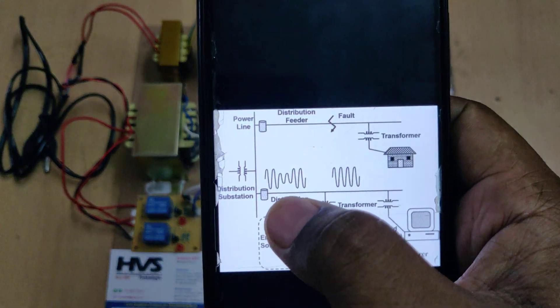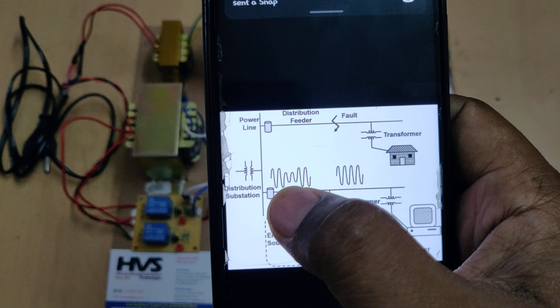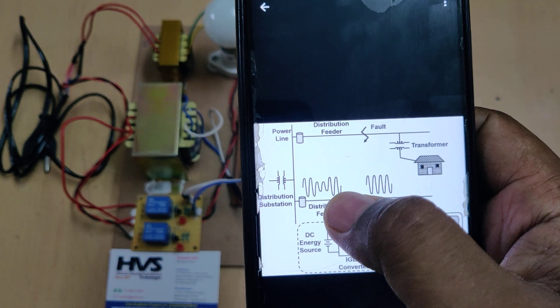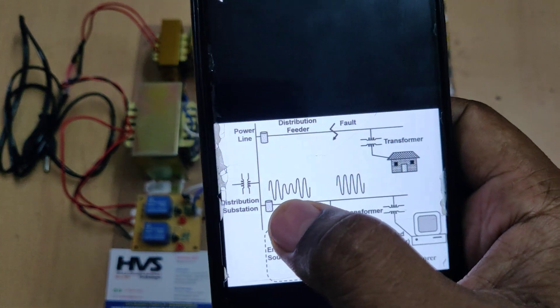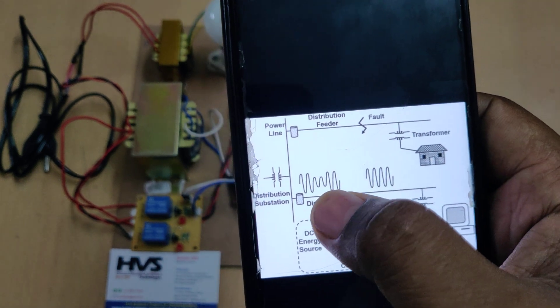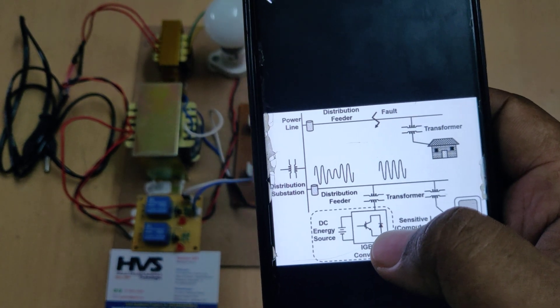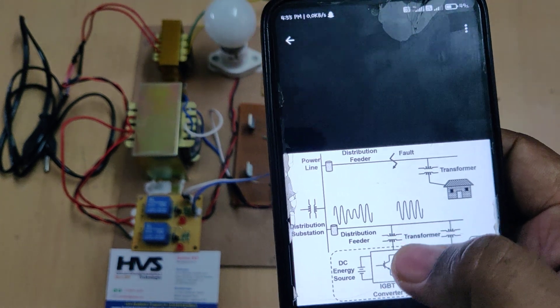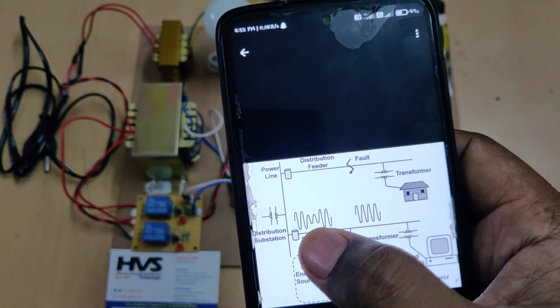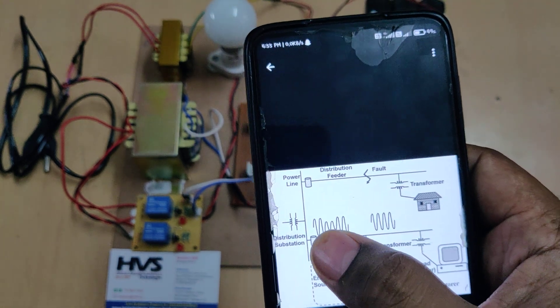Whenever voltage sag occurs — normally a sine wave is provided to the load — if there is any voltage sagging in the single phase, it will be rectified by the dynamic voltage restorer. The system continuously monitors voltage levels, and whenever a voltage sag is detected, it generates a signal with the same frequency and same voltage level to compensate the sagging loss, providing uninterrupted power supply at the output.